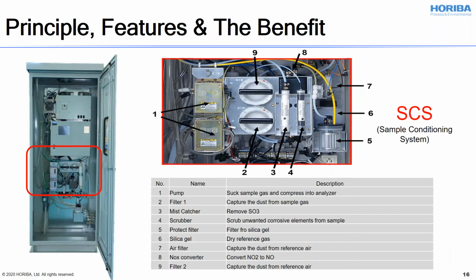All right. This is the picture of the inside of the cabinet with the sample system. It is, you know, a good compact design, and I see the box in red here. This is the zoomed picture of the sample system. As you can see here, the pump, a filter, a mist catcher and a scrubber. And number 5 protects the filter, and there are silica gel, an air filter, and the NOx converter behind this, number 8. So the point I want to highlight here is that everything is designed for ease of maintenance. You can access everything from the front side, which is always a better way to do it.